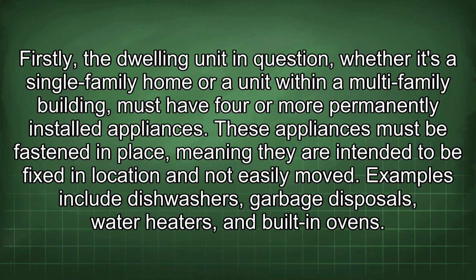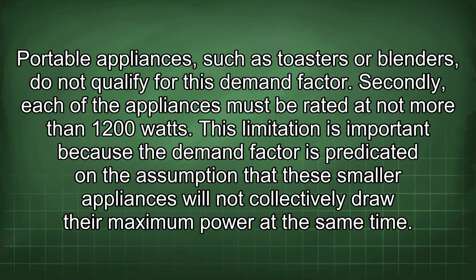Firstly, the dwelling unit in question, whether it's a single-family home or a unit within a multi-family building, must have 4 or more permanently installed appliances. These appliances must be fastened in place, meaning they are intended to be fixed in location and not easily moved. Examples include dishwashers, garbage disposals, water heaters, and built-in ovens. Portable appliances, such as toasters or blenders, do not qualify for this demand factor.